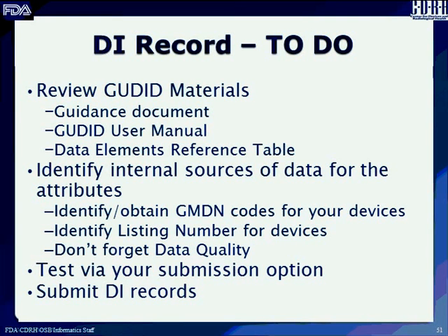At this point, I'm going to say I'm ready to submit this. Let me go ahead and review. It says there is an error. What is the error? This is part of passing all the business rules. This is where the system is saying, do you have all the information you're supposed to, and is the information that you provided correct? It tells me that I did not choose single use. Single use is a required field, and I didn't enter it, so I'm going to say yes, this is a single-use device. Now, can I please pass review?